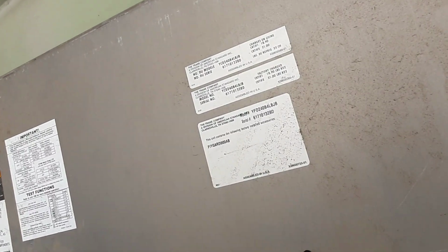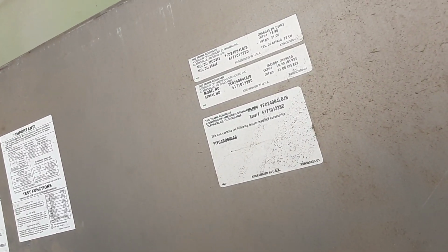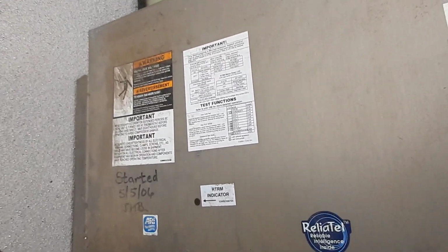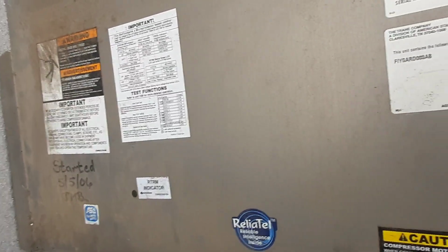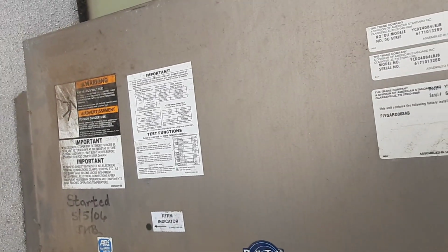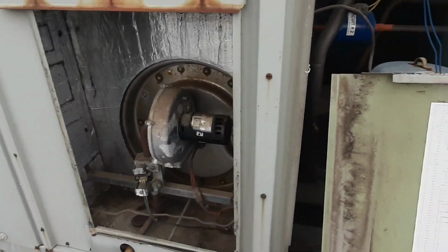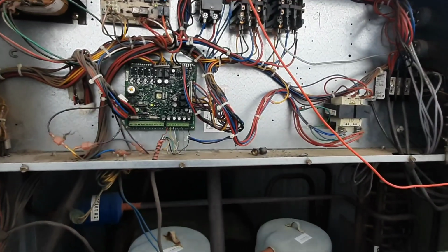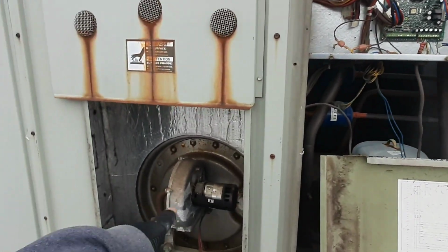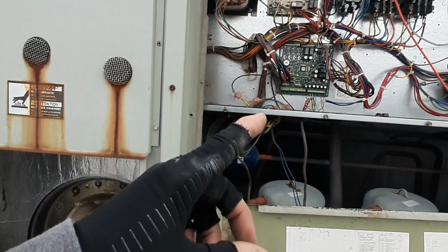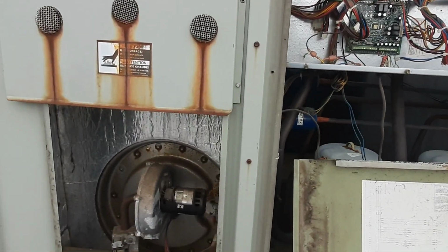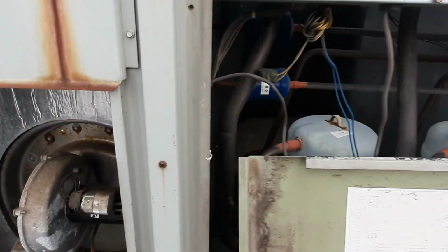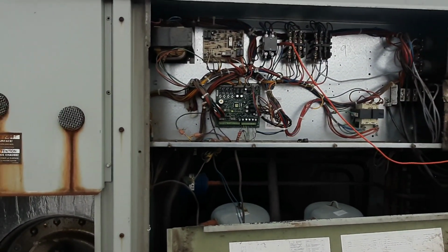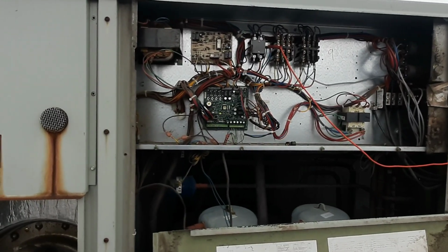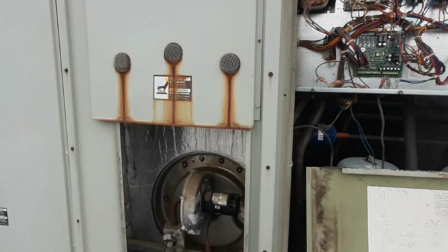Or even how old this thing is. Let's see. I don't know about that model number. Or the serial number. Might be a 2010. There he goes. There's a startup date, 06. So it's not a 2010. So it's an old one. Blower went off. Wonder if maybe it fired. It got its time delay, and then the blower was cycling because of a limit or something, maybe. I mean, it's time delays in the RTRM. I don't know that the blowers keep running. Sometimes the blowers will keep running if you got a limit trip or something.